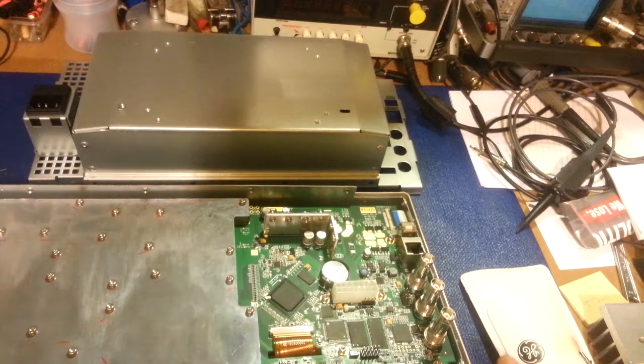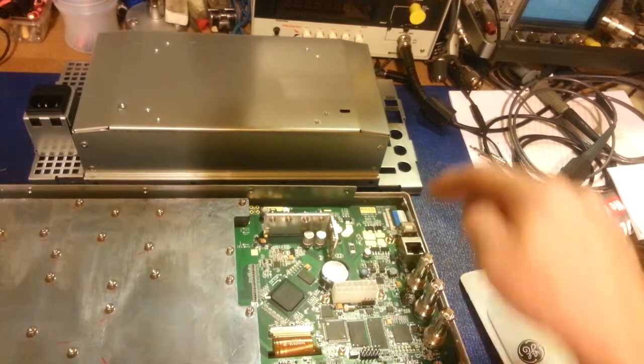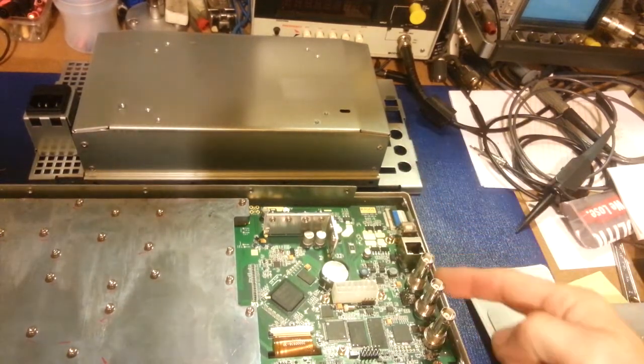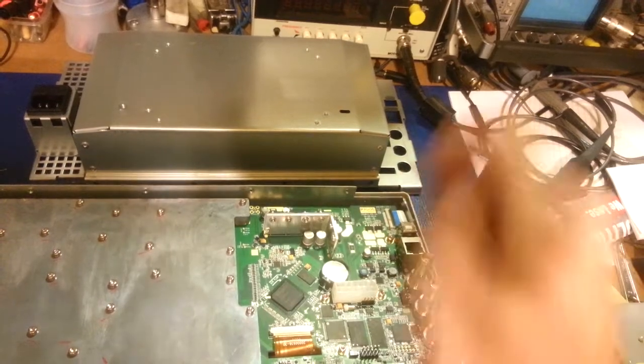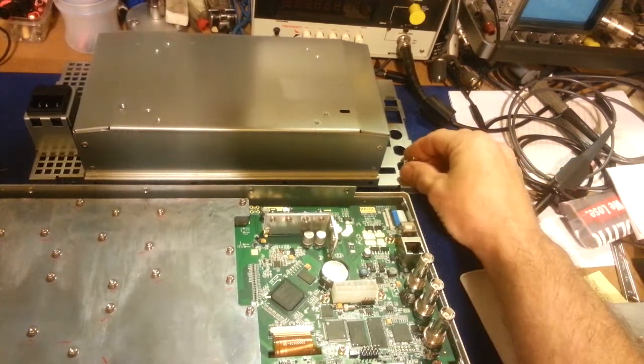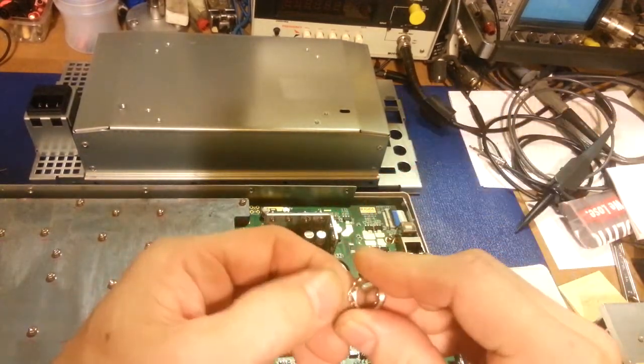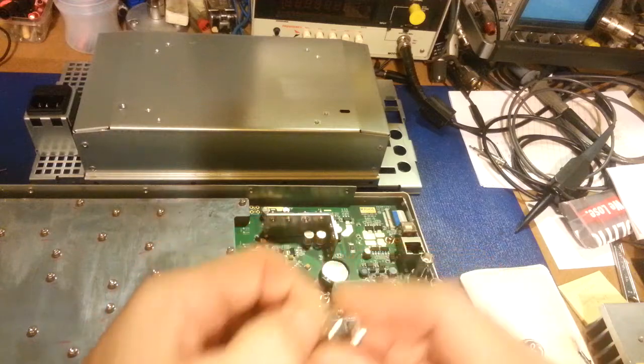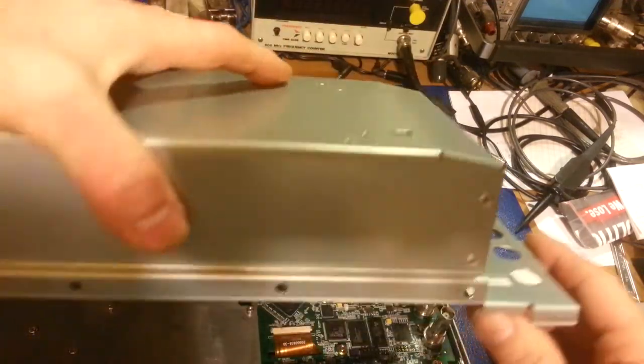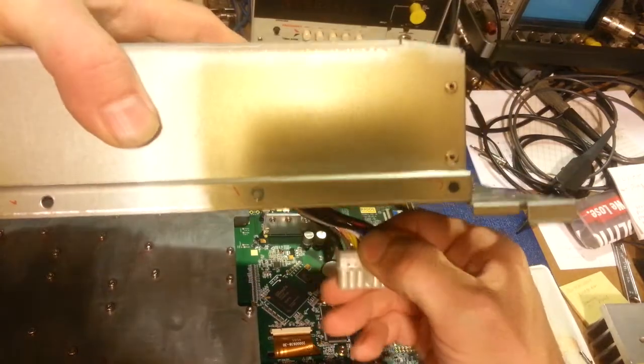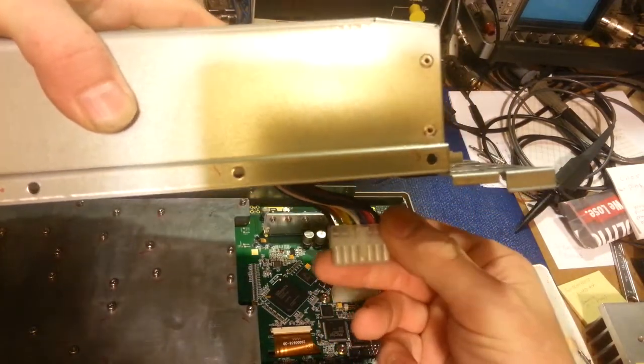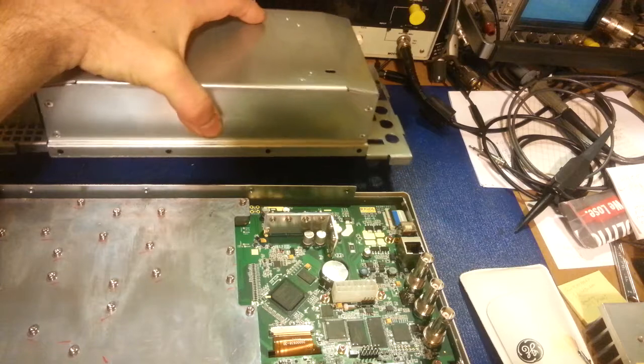And then you will also need to take off three nuts where these BNC jacks protrude out through the back of this shield, there's a nut on the outside. So you'll need to take these three nuts and star washers off. Once you have those off, lift the power supply module up, depress the little release latch here, and disconnect the power supply module off of the main circuit board.